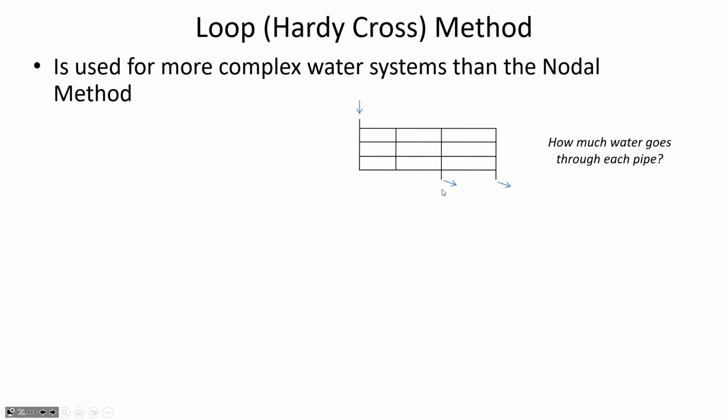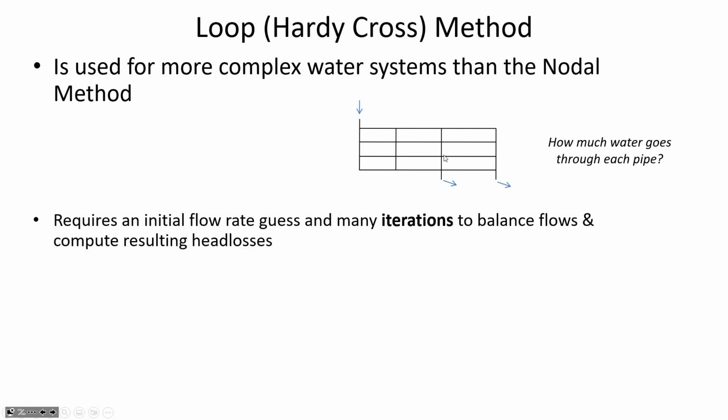It's the same. That same principle applies in the Hardy-Cross method. And the whole essence of this method is trying to balance what flow rate it would take so that we have the same head loss through each route that the water could potentially go through. So it's going to be a series of complex adjustments, corrections, with the overarching goal of calculating the flow rate that would bring balance so that regardless of which route the water is taking, it has the same amount of energy loss. That's what's working in the background of this method that you're going to learn today.